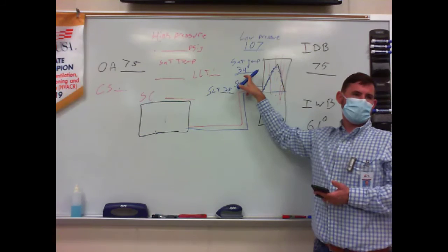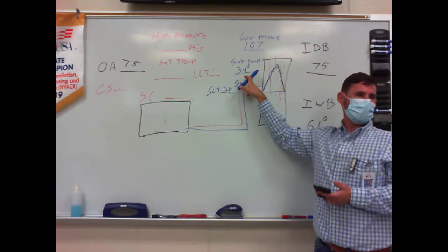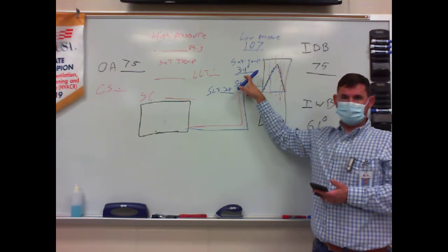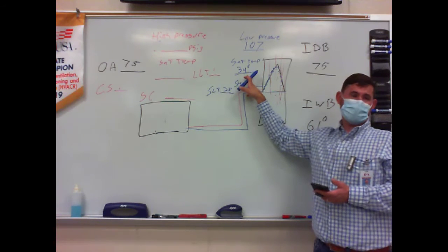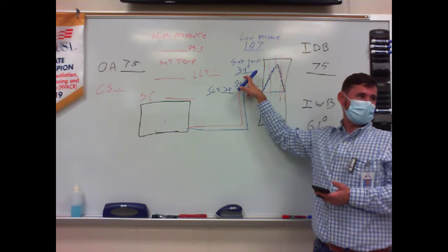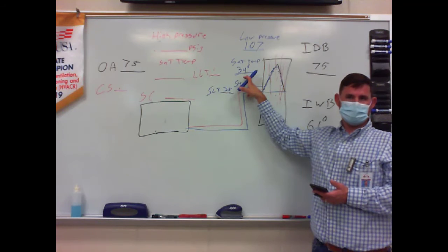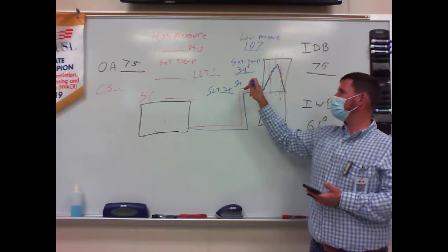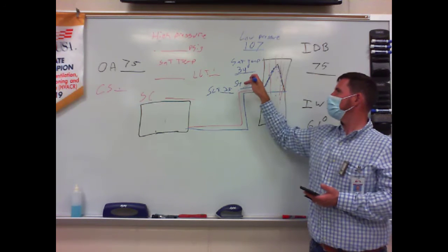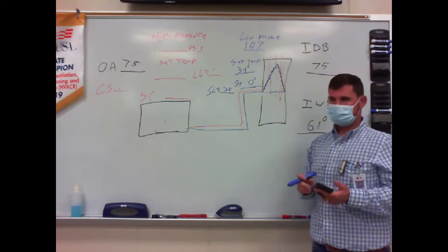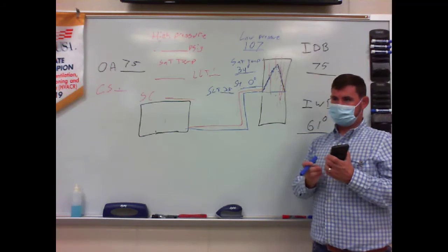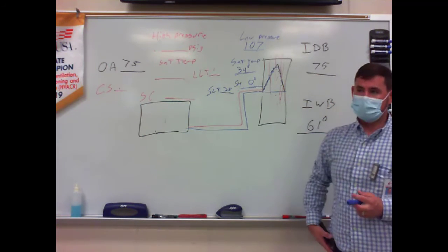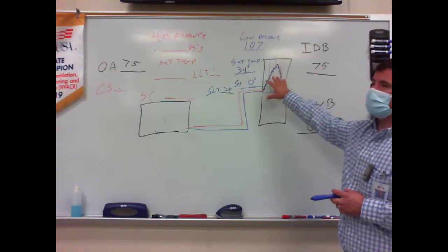What do you think is going to happen when I start removing refrigerant? It's going to go down, right? And I'm going to start freezing that coil up. So what was my superheat? 0 degrees? That means too much refrigerant, or? Yeah, it means there's too much refrigerant in there.